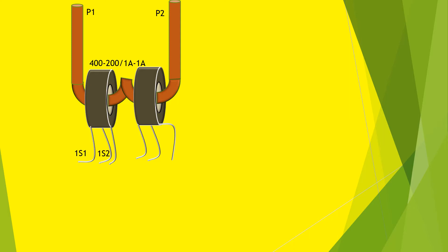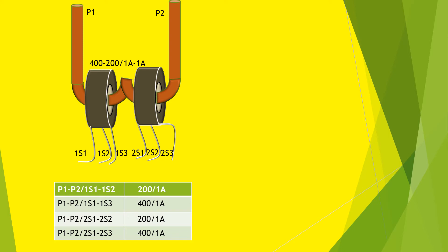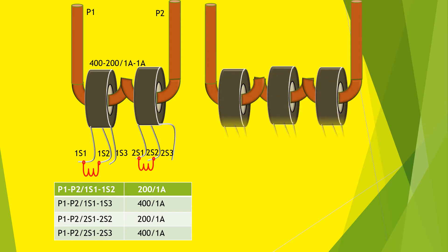The rating is 400/200 by 1/1 ampere, with two settings at the primary side — 400 ampere and 200 ampere — available depending on lead connection at the secondary side. To allow 400 ampere normal current along P1 and P2, secondary leads of both cores are connected at 1S1 and 1S3, and at 2S1 and 2S3. To allow 200 ampere normal current, secondary lead connections are at 1S1 and 1S2, and at 2S1 and 2S2.